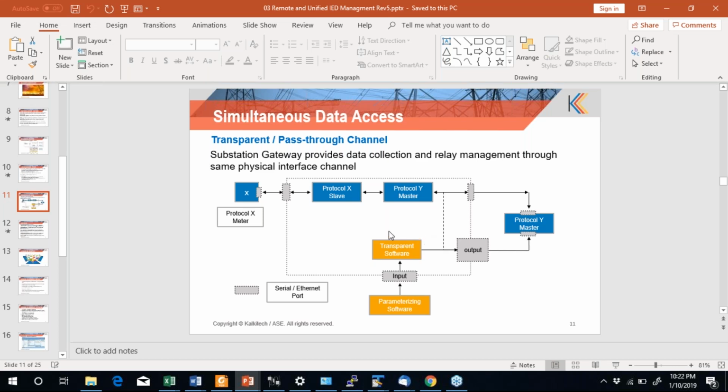If normal priority is put for the transparent channel, it goes in a cycle stealing approach. One main channel message gets processed, then it checks whether there are any messages on the transparent channel. If there are, that message will be processed and its reply sent. The next message of the main channel will be sent, and its reply sent.